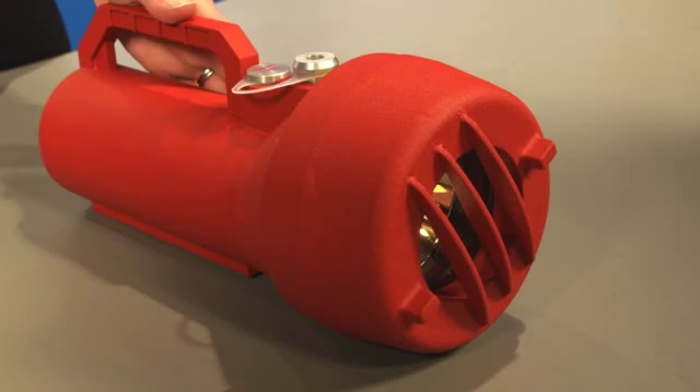Regular testing is an important and crucial step to ensure both optimal protection and operation of all Flame Guard 5 products, in addition to increased product life. The test lamp is an explosion-proof fire simulator that provides a high-energy broadband radiation source emitting sufficient energy in both the ultraviolet and infrared spectra. Designed for the Flame Guard 5 product family, the test lamp offers a rechargeable replaceable battery, easy grip handle, battery charger, status indicator, and microcontroller.